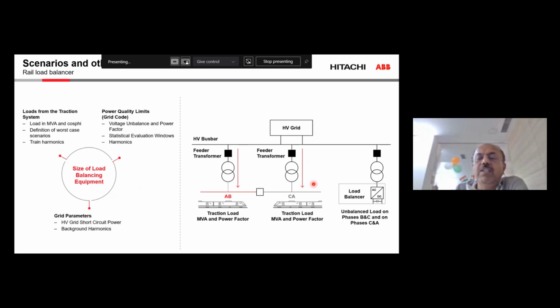Having decided what is the size of the load balancer, you can see one scenario here that two railway stations or the metro feeding stations are connected to a network that is called as high voltage grid, and then when they are connected and balancing the overall power drawn from this railway going from AB to CA segment, but when one station is down, for example this station feeding to the CA is down, the entire current is drawn from only two phases. Power is fed from the one feeding station, so the unbalanced factor will dramatically change when we have this kind of scenario compared to what we had in the previous where two stations are acting.